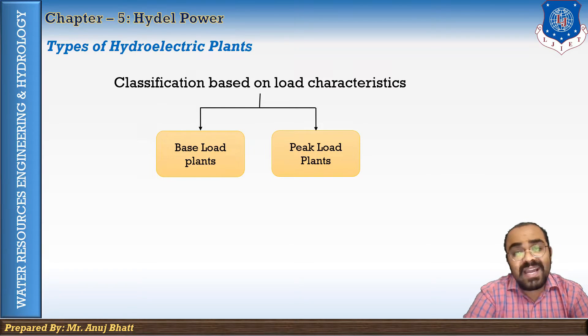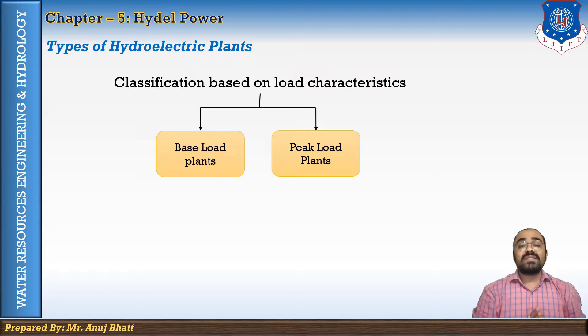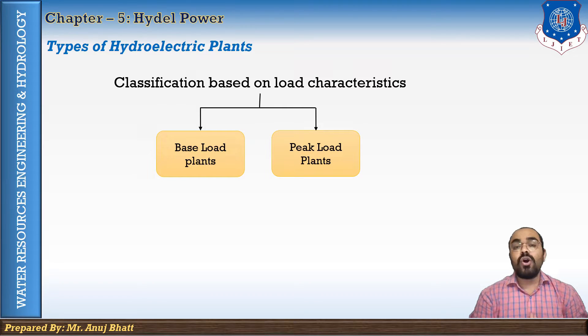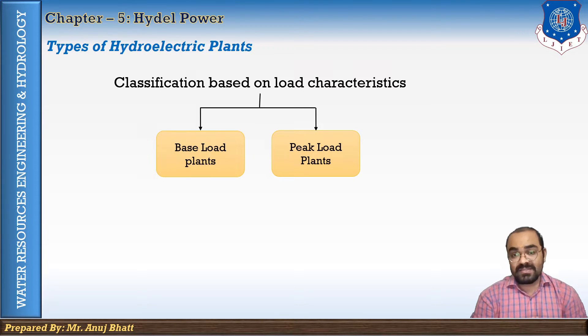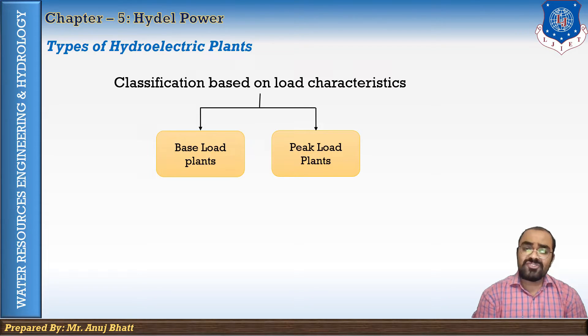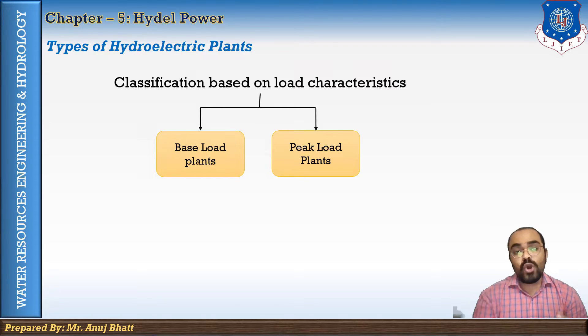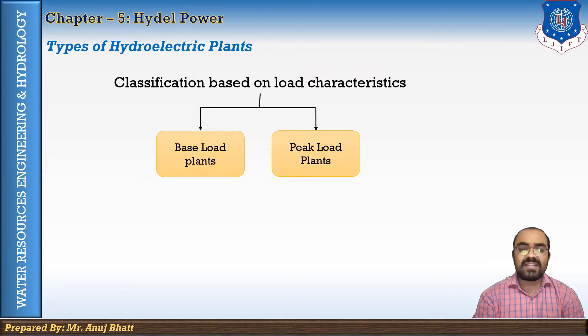A peak load plant is designed to take care of the peak load of the power system. It operates only during the period of peak load. Pumped storage plants are usually designed as peak load plants. A run-of-river plant with pondage can operate either as a peak load plant or as a base load plant, depending upon the size of pondage.